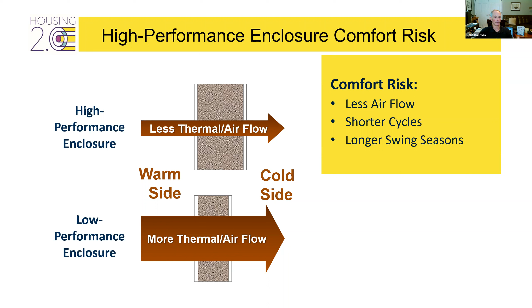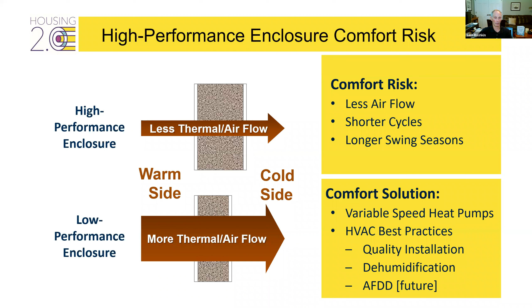So we don't just build high performance buildings, we do comfort solutions: variable speed heat pumps, HVAC best practices, ensuring quality installations with airtight ducts and proper airflow, strategies for dehumidification—whether dedicated dehumidification equipment or variable speed compressors that throttle down and function like a dehumidifier—and automated fault detection and diagnostics in the future will also assure systems installed are ready for low load homes.